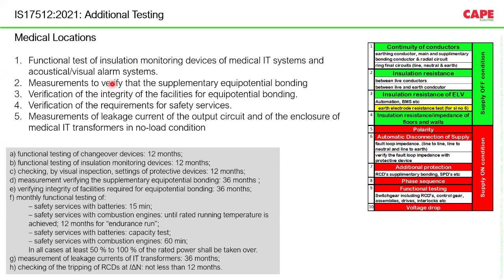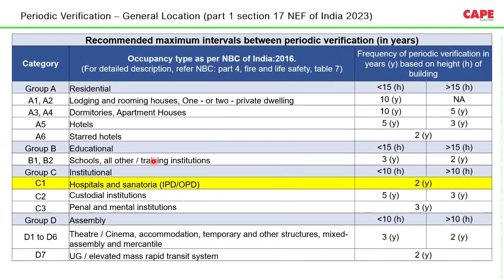The second and third are both related to shock reduction: supplementary equipotential bonding, and facilities for equipotential bonding, the efficiency of these bondings. Please note that bonding means you take a wire and connect it to metal parts. Then you check and find out the actual potential difference between these two parts, and it should be lesser than 40 millivolt, for example. Then safety services, and the standard also recommends the frequency of these checkings as per the standard.